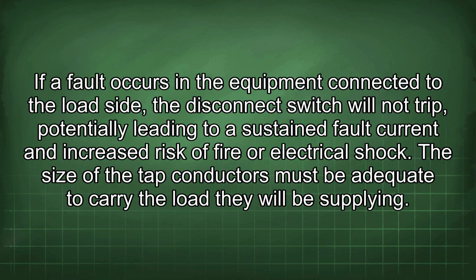If a fault occurs in the equipment connected to the load side, the disconnect switch will not trip, potentially leading to a sustained fault current and increased risk of fire or electrical shock.